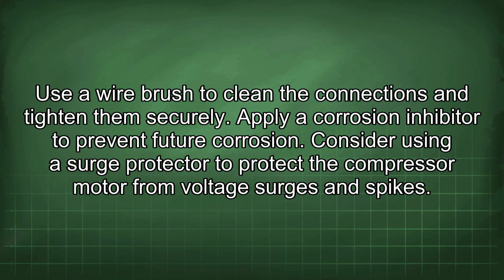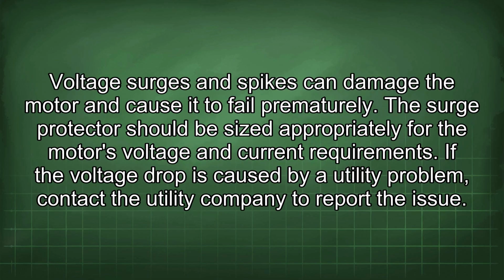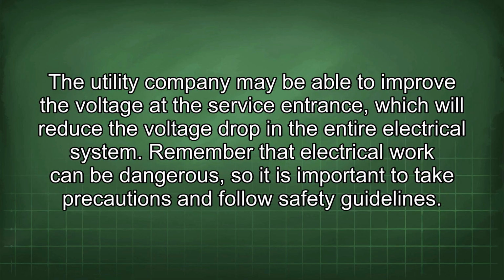Consider using a surge protector to protect the compressor motor from voltage surges and spikes. Voltage surges and spikes can damage the motor and cause it to fail prematurely. The surge protector should be sized appropriately for the motor's voltage and current requirements. If the voltage drop is caused by a utility problem, contact the utility company to report the issue. The utility company may be able to improve the voltage at the service entrance, which will reduce the voltage drop in the entire electrical system.